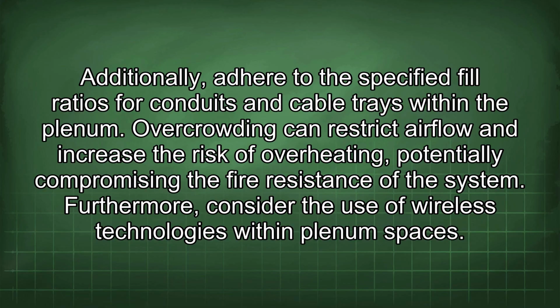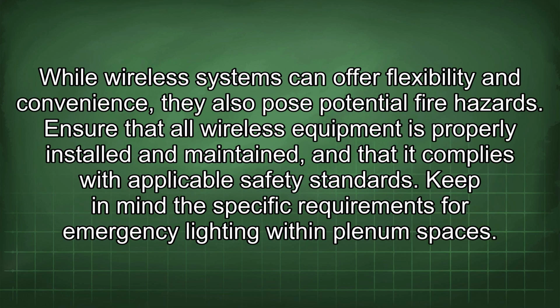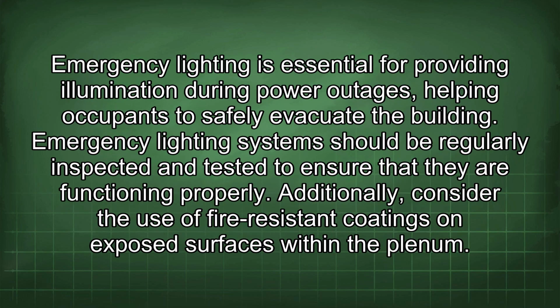Furthermore, consider the use of wireless technologies within plenum spaces. While wireless systems can offer flexibility and convenience, they also pose potential fire hazards. Ensure that all wireless equipment is properly installed and maintained, and that it complies with applicable safety standards. Keep in mind the specific requirements for emergency lighting within plenum spaces. Emergency lighting is essential for providing illumination during power outages, helping occupants to safely evacuate the building. Emergency lighting systems should be regularly inspected and tested to ensure that they are functioning properly.